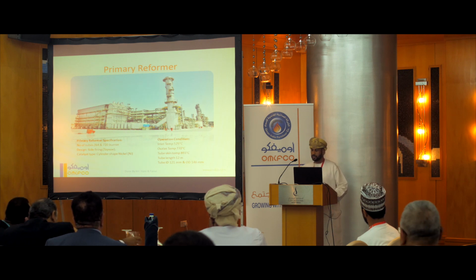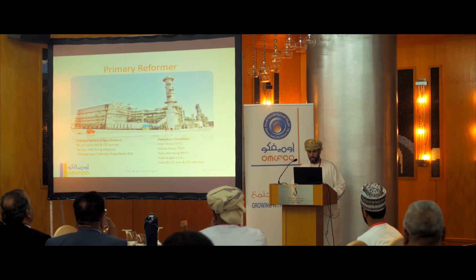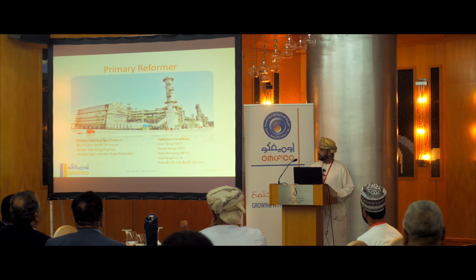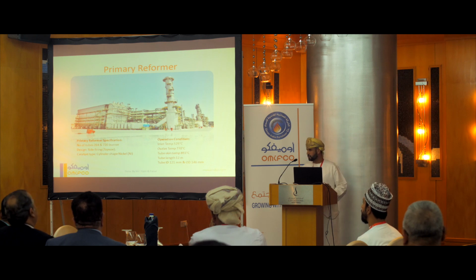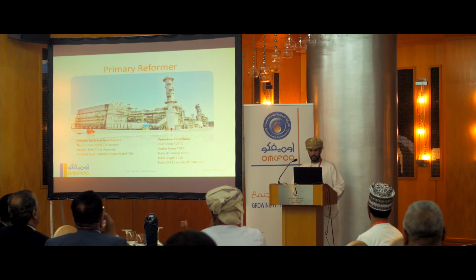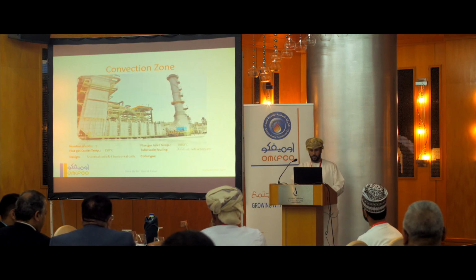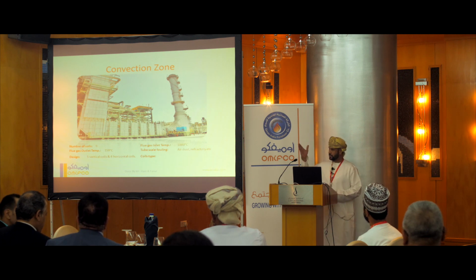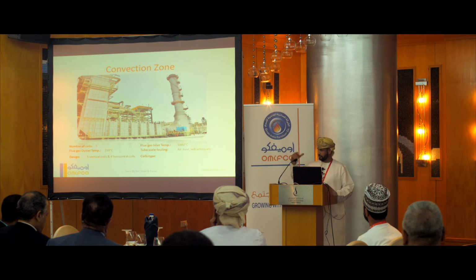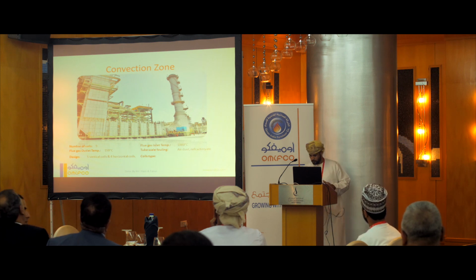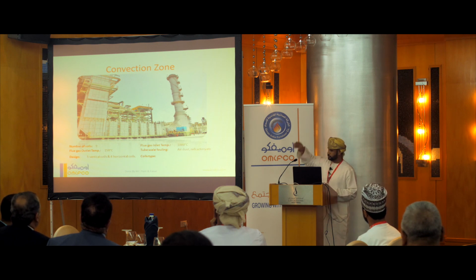And the outlet temperature is 770 degrees centigrade. Tube skin temperature design is around 893 degrees centigrade, but we are working at somewhat less than that, and we don't face any problem till now with any tubes. This is the convection zone. We have 9 coils in the convection zone. The first 3 from the top are plain coils, and the remaining 6 are the fin type of coils. We have different types of coils: steam coil, NG coil, BFW coil and air coils. This is all the 9 coils from the top down to the bottom.